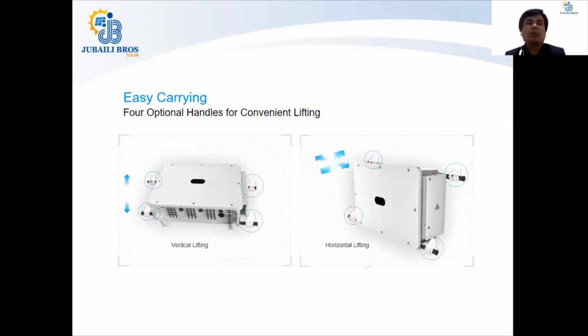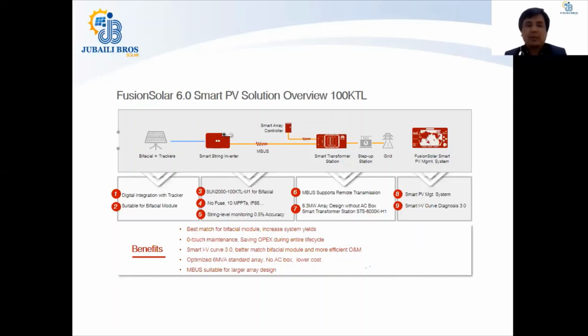For easy carrying, Huawei can provide you optional handles. These can be used for vertical lifting or horizontal lifting. Now, the 100 KTL inverter, as I said, is made adaptable for bifacial modules especially, which can also be used with standard monofacial PV modules. The inverter is integrated with the tracker control connection. When you're using trackers, you usually have a controller that needs data from the generation point to control the angle of the bifacial or monofacial modules. In that case, Huawei has also made an input to the inverter for the controller. It is highly suitable for bifacial.